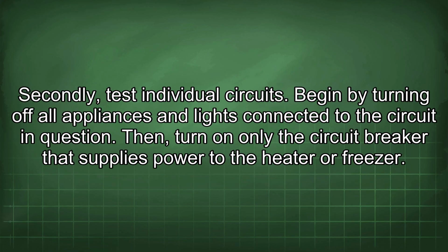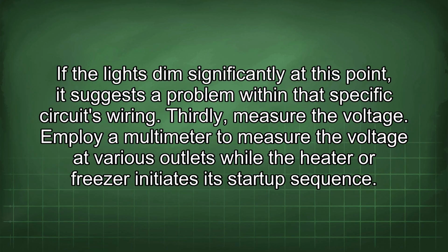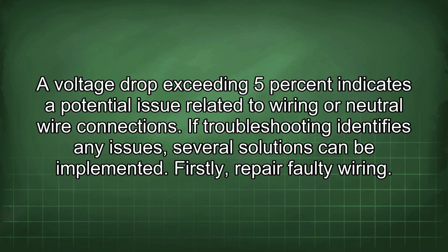Secondly, test individual circuits. Begin by turning off all appliances and lights connected to the circuit in question. Then turn on only the circuit breaker that supplies power to the heater or freezer. If the lights dim significantly at this point, it suggests a problem within that specific circuit's wiring. Thirdly, measure the voltage. Employ a multimeter to measure the voltage at various outlets while the heater or freezer initiates its startup sequence. A voltage drop exceeding 5% indicates a potential issue related to wiring or neutral wire connections.